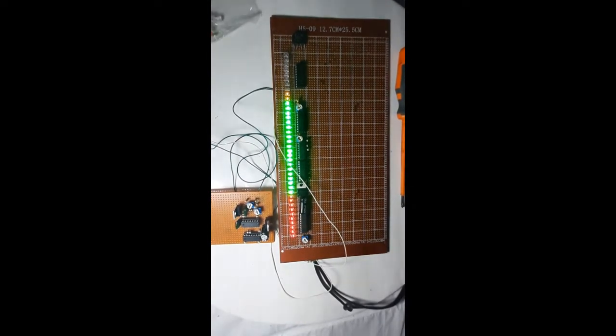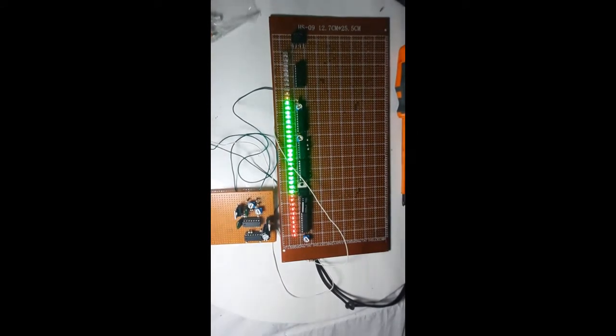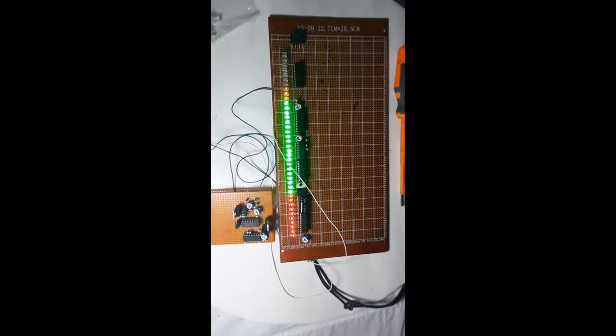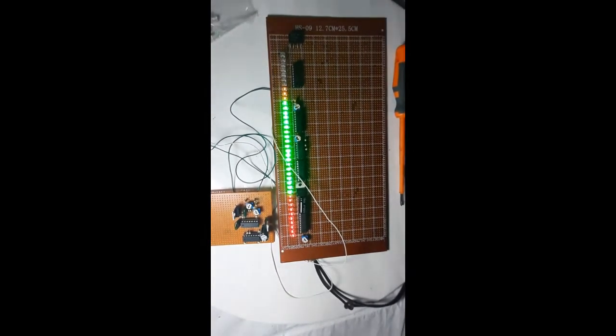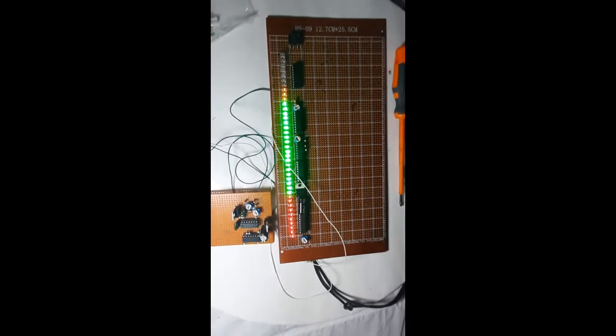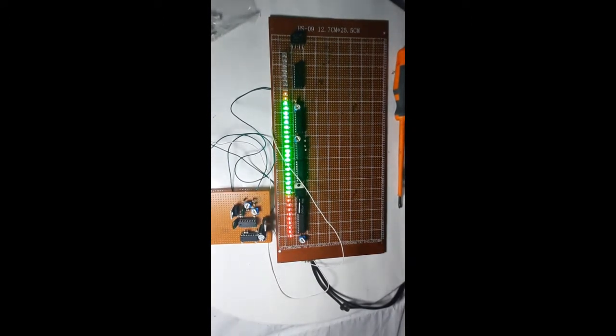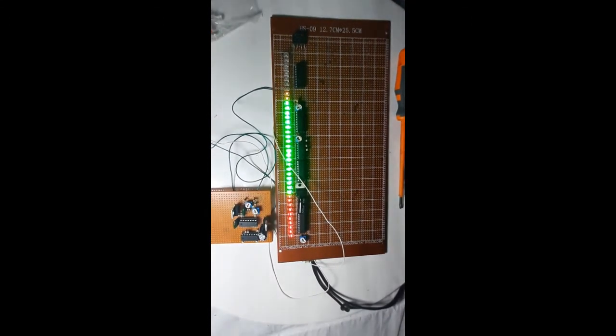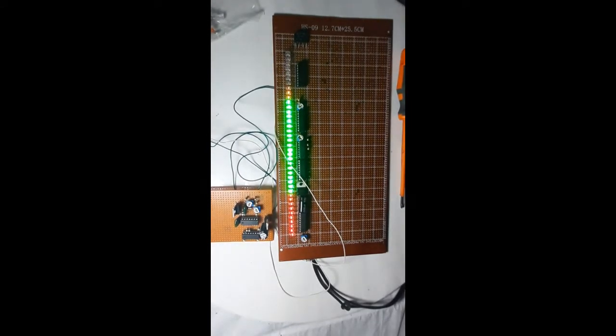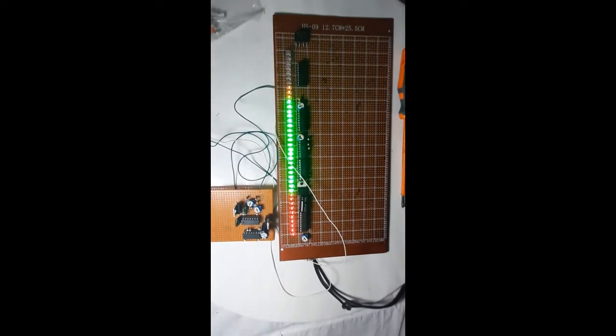As an example, the voltage standards are 0 to 5 and 0 to 10, two standards out of many. And for the current standards, the most popular is the 4 to 20 milliampere current loop. 0 to 20 is also still in use, but of course 4 to 20 is the one in wide use. So here what I have used is the 4 to 20 milliampere current loop.